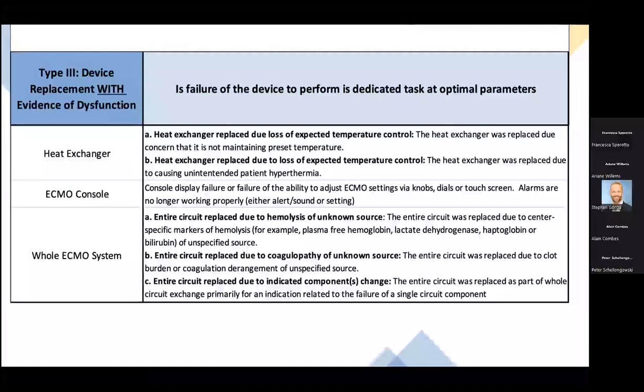Then we have the ECMO console. The console display fails, with loss of the ability to adjust ECMO settings via knobs, dials, or touch screen. Alarms are no longer working properly, either the sound or the visual alert. Then the whole system can be replaced, and they have three subcategories, A, B, and C.